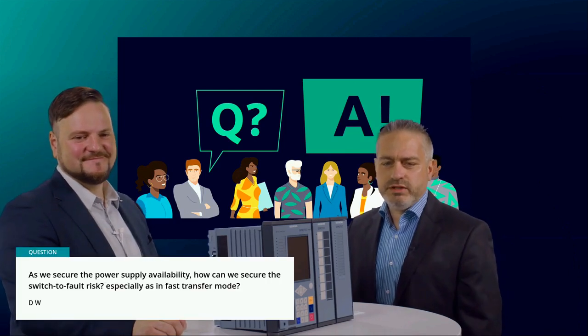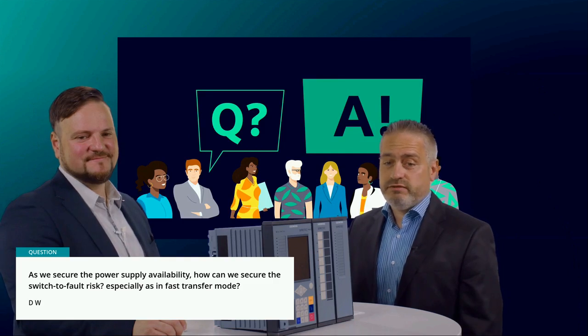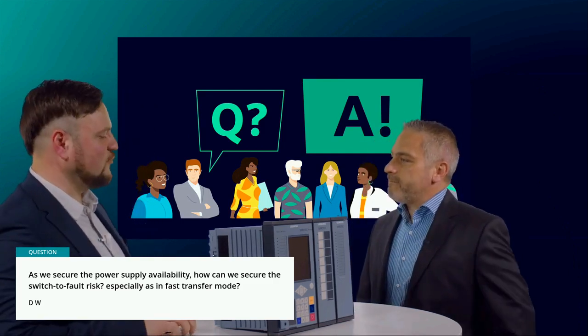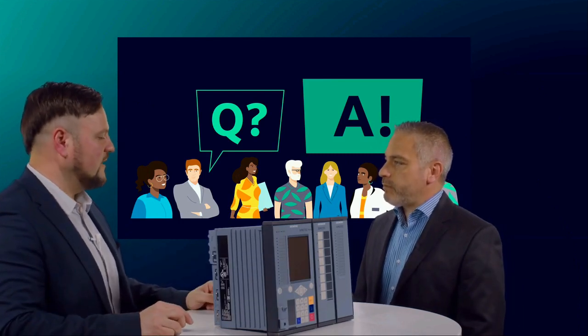As we secure the power supply availability, how can we secure against switch onto fault risk, especially in fast transfer mode? This could be a reason, but we also have implemented a functionality like switch onto fault. That means if there is a fault on the alternative incomer, we switch onto that fault. First we have a readiness and unreadiness check, so we're checking that the alternative incomer is fault free. But if there is a fault, we immediately trip the breaker. And of course, if we have a fault on both incomers, then we have to block the HSBT system, and in that case we lose the motor bus.